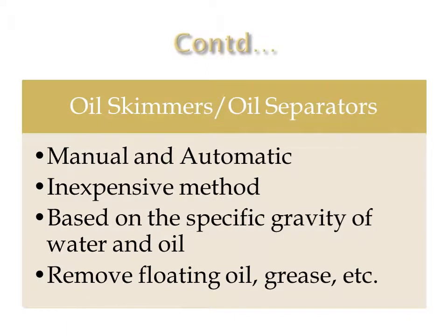Oil skimmers and separators. These are used for the separation of oil or grease from the wastewater, and these are available manually operated as well as automatically operated. This is an inexpensive method that separates the oil and grease due to their low density in comparison to water. As a result, these materials float over the surface, from where they are skimmed off and sent to the digesters along with the settled materials. In this way, oil skimmers and separators separate the floating oil and grease from the wastewater.